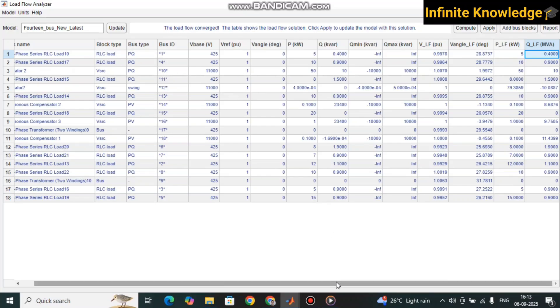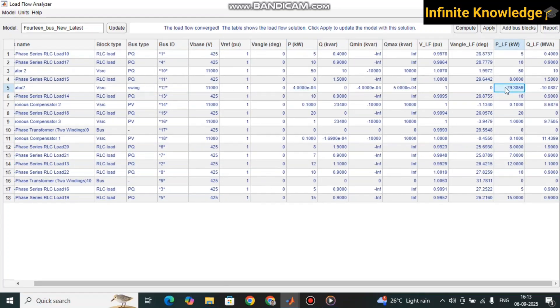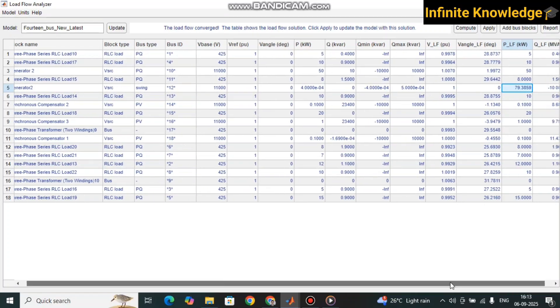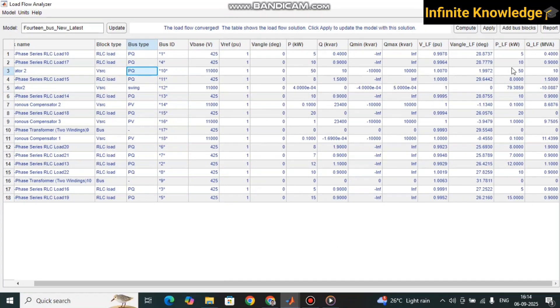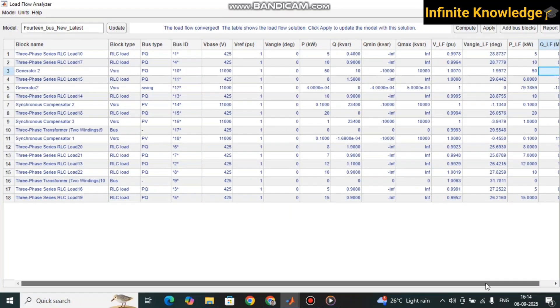You can see the swing generator is feeding 79 kW of active power into the system. If you add all the load kilowatt requirements you will get this value, because all kilowatt demand is fed by the swing generator. There is also a slight contribution from the PQ generator, which has a maximum capacity of 50 kW and 100 kW as I defined.